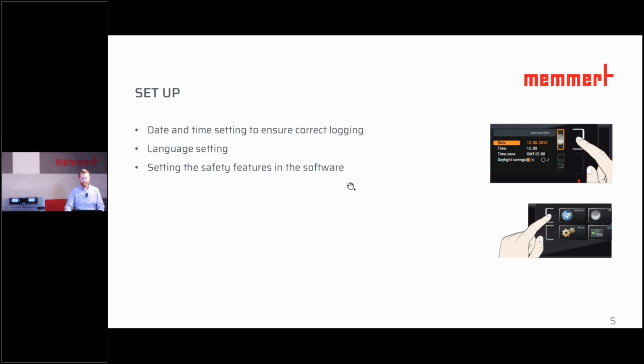These safety features can be, for example, the choice between an adjustable over temperature controller, which is then equal to security class 3.1, or an adjustable over temperature limiter, class 2. Each device must be equipped with a mechanical temperature limiter, which is equal to safety class 1.